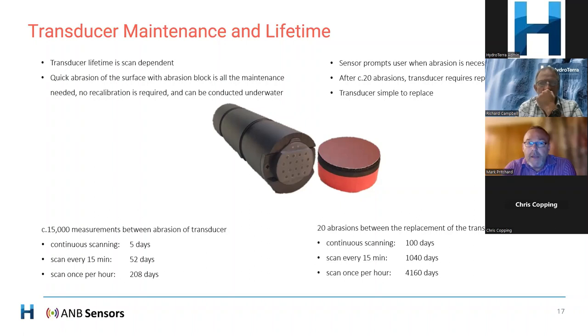So that's what we call abrading the sensor, and we need to do that every 15,000 measurements. After you've abraded the sensor 20 times, you then need to replace the transducer. So 20 abrades means 300,000 measurements. On the bottom left of the screen, you can see you need to replace the actual transducer in more or less about 3 years if you're scanning every 15 minutes. So it really is minimal maintenance and extremely minimal ongoing costs for managing the sensor.